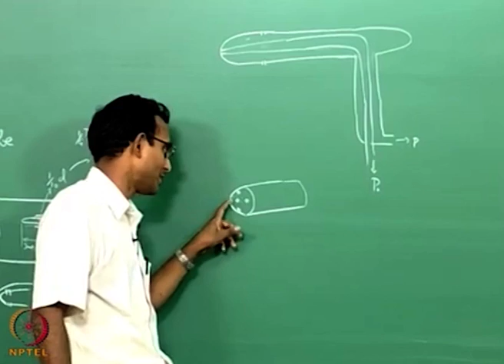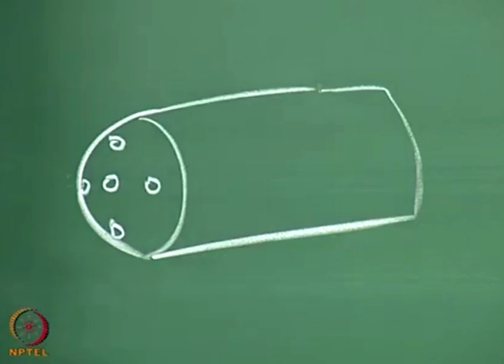This probe can measure the angle of attack of the flow with respect to the probe also. If I send a flow like this, this is going to measure close to stagnation, and that is going to measure much lesser. The differential between these two will give me my pitch angle. The differential from this side versus that side will give me the yaw angle. And if the flow is going straight in front, then I can use these values with the center value to get a velocity, but that has to be calibrated. It is not going to be the same value as the top probe, because it is not going to give you static pressures on these 4 holes. They are going to give something between static and stagnation, and that has to be calibrated.